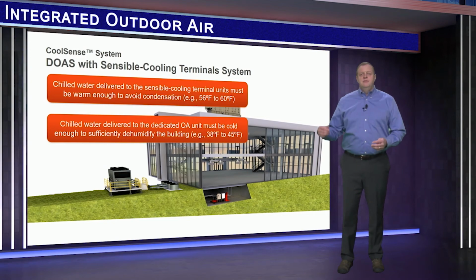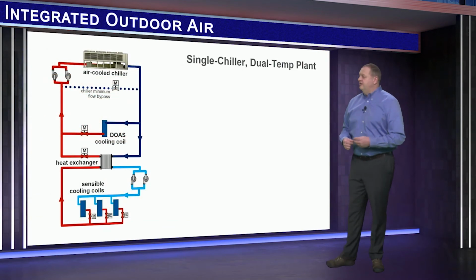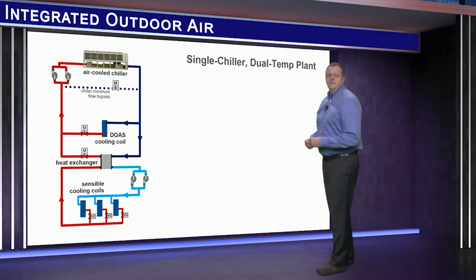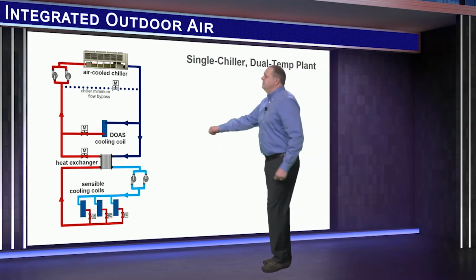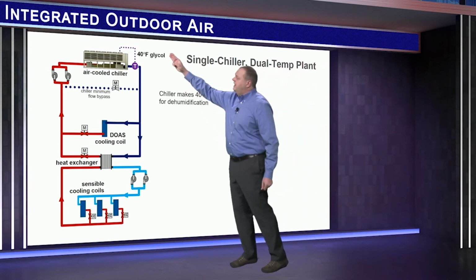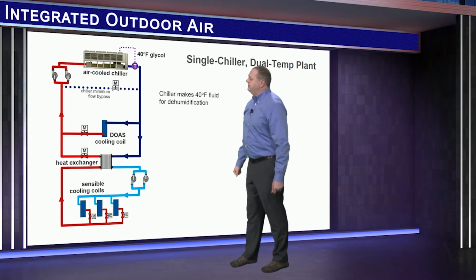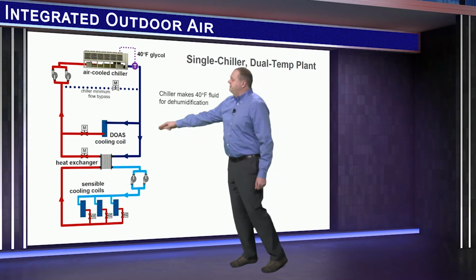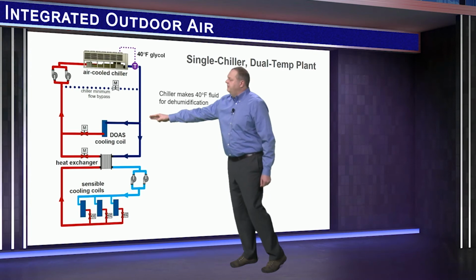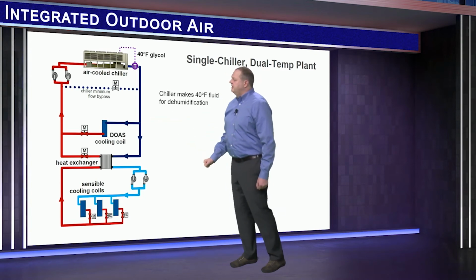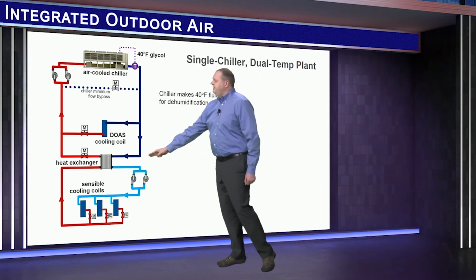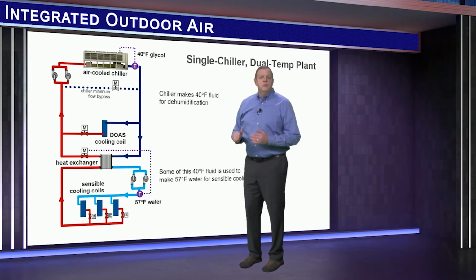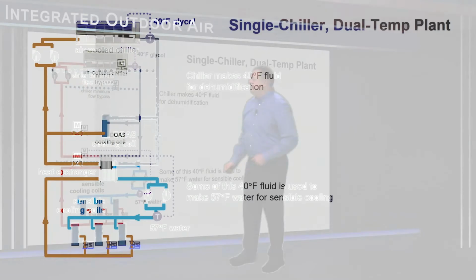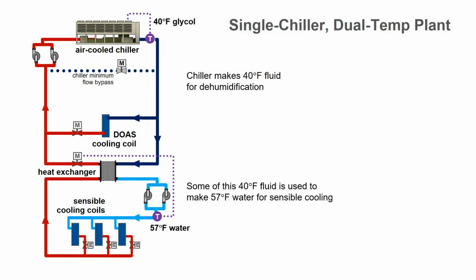So I'll start with maybe the most basic configuration, a single chiller dual temperature plant. Here, the chiller produces 40-degree fluid, either a water or water glycol mixture. Some of this fluid is distributed to the cooling coil in the dedicated outdoor air unit for dehumidification, while the rest passes through a plate and frame heat exchanger with a valve that's controlled to produce 57-degree water on the other side. This warmer water is then distributed to the sensible cooling coils in the terminal units.